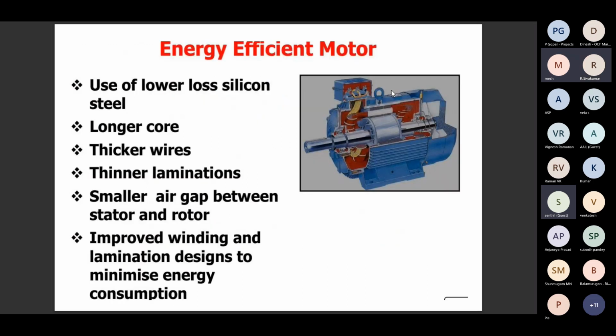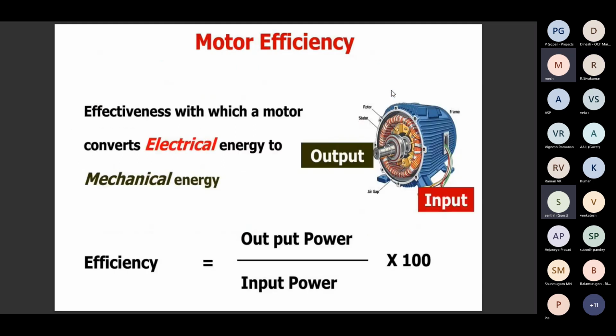So this is the inside of an energy efficient motor. They use lower loss silicon steel, longer core, thicker wires, thinner lamination, a smaller air gap between the stator and the rotor, and improved winding and lamination designs to minimize energy consumption. These are the steps taken by the original equipment manufacturers, OEMs, for making energy efficient motors. Next one. So basically, efficiency is nothing but output power divided by input power. Normally, when a motor is rated as 10 HP, what is it?